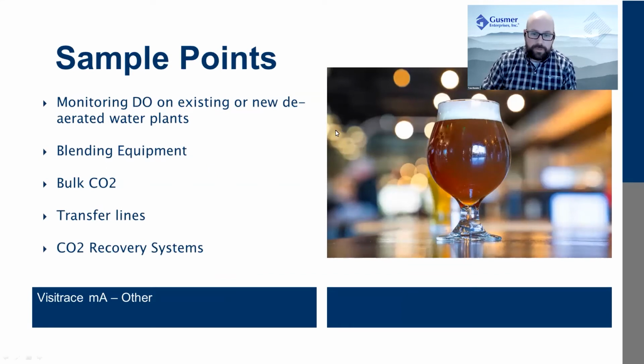Some other sample points outside of packaging and wort fermentation would be your deaerated water plants. If you have a current deaerated water plant, or are looking to purchase one, it's important to measure the dissolved oxygen to ensure it's working correctly. Also, if you're using something like a buffer tank, make sure the water going out of that tank is within spec.